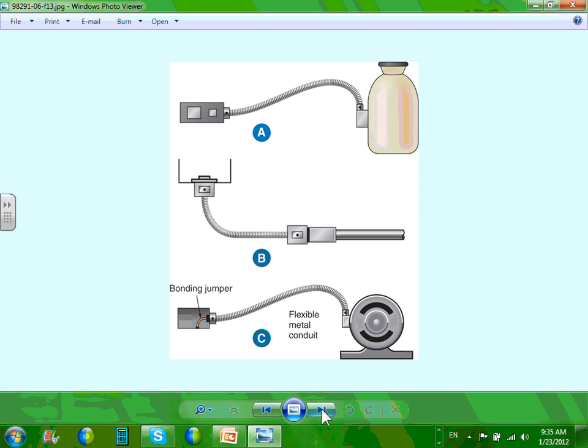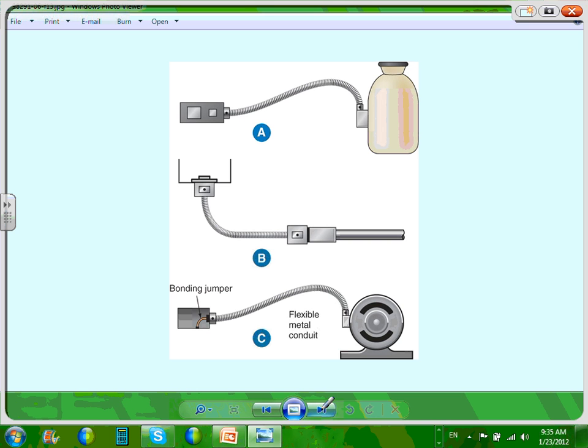When you tie to equipment, look at that. There's a coupling that takes you from EMT into flex, or you have to go through boxes. When you tie to equipment that vibrates, does the fan vibrate? I mean, does the light here vibrate? No. For the most part, no.